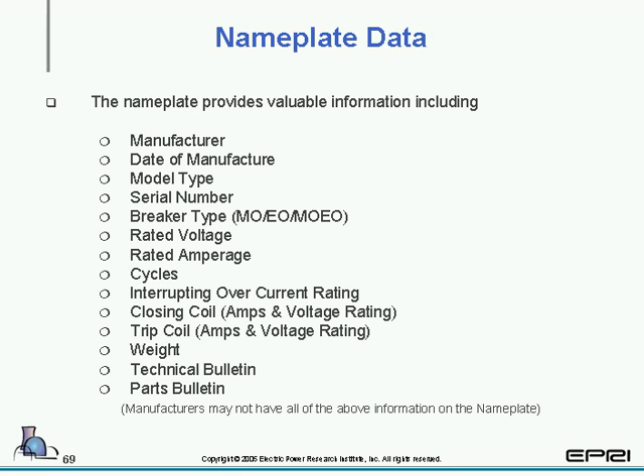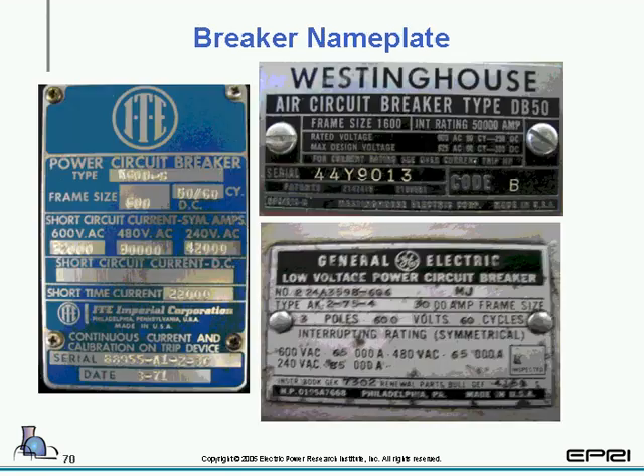The nameplate. The nameplate provides valuable information, and we have a list of items. Not all manufacturers will have all this information, and we have some examples. We have I.T.E., we have a Westinghouse, and we have a GE. Some of the number one things you will find on the tags are the type of breaker, the voltage, and the current.